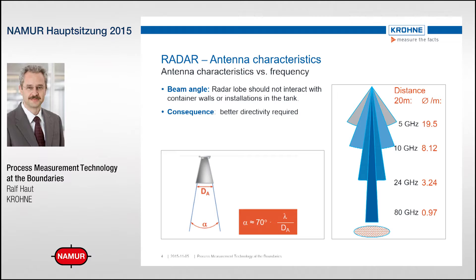At 5 GHz, the lobe diameter at 20 meters distance will be 20 meters, likely causing parasite reflections. To reduce lobe diameter, higher frequency is needed: 10 GHz provides approximately 8 meters, 24 GHz approximately 3 meters, and 80 GHz provides approximately 1 meter of lobe diameter at 20 meters distance — excellent performance for tall, slim tanks and also smaller tanks.